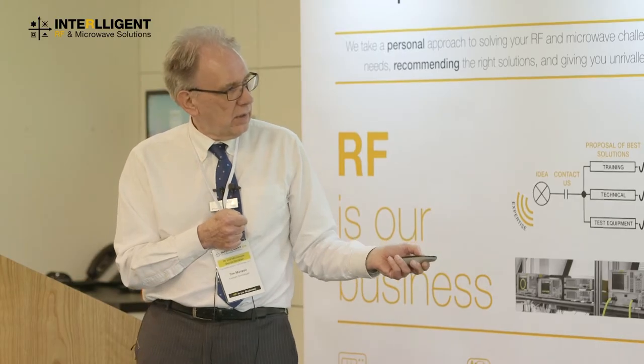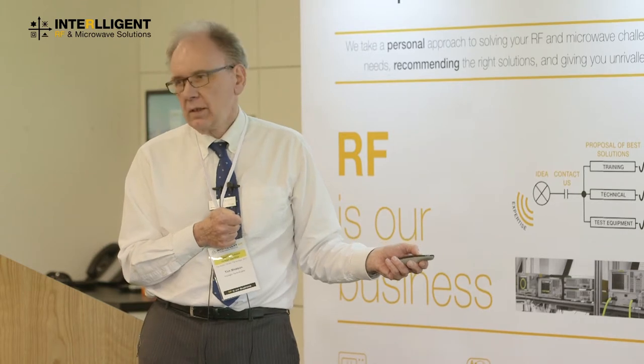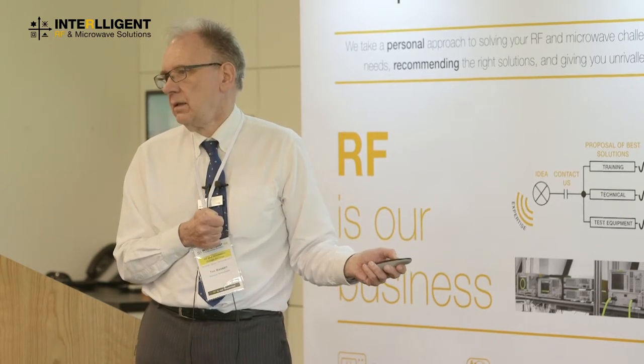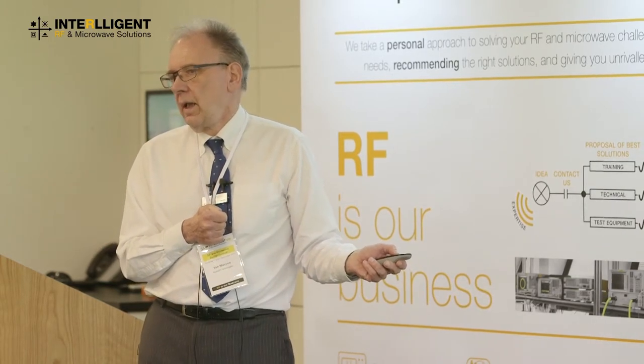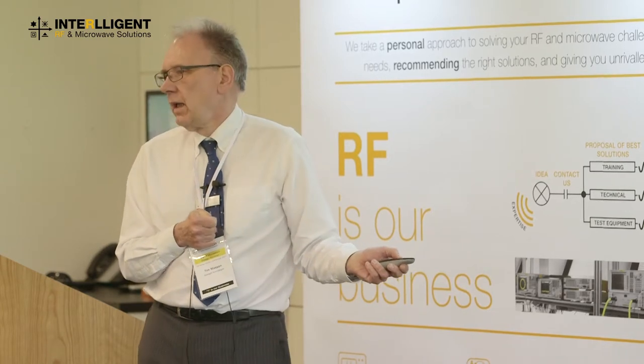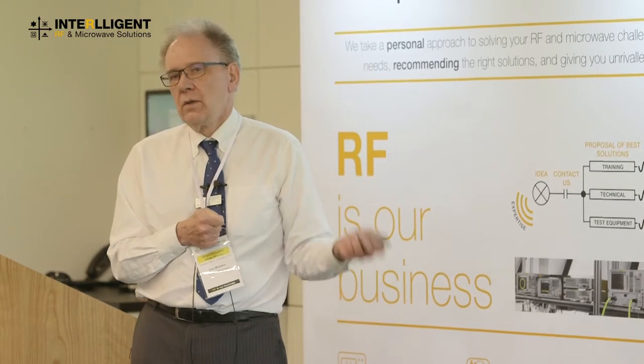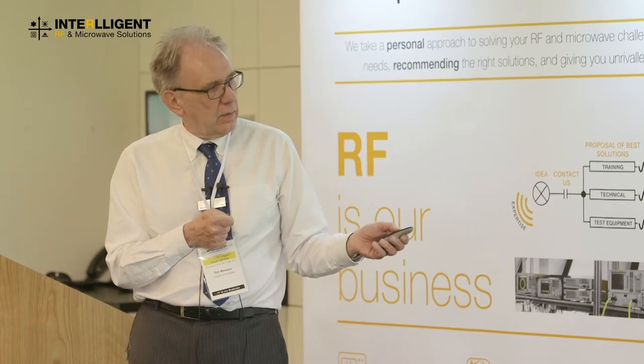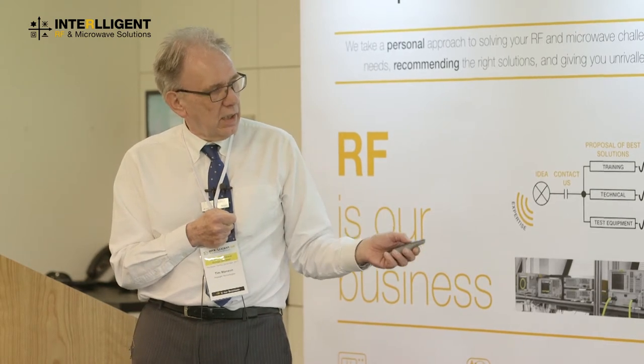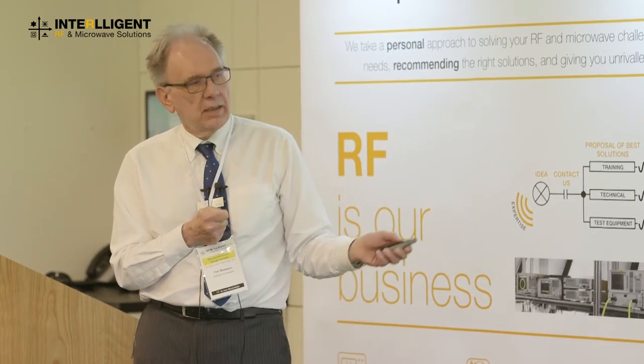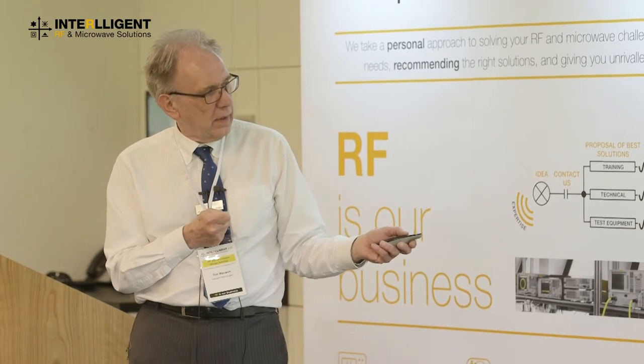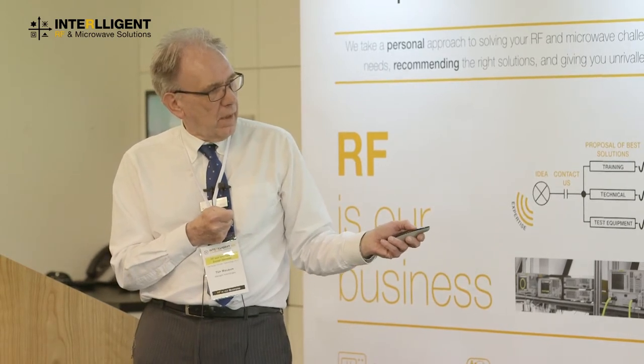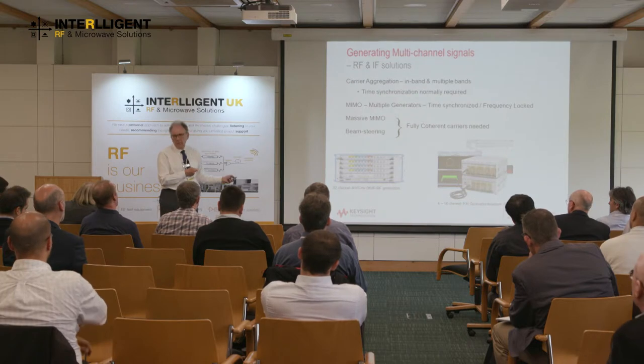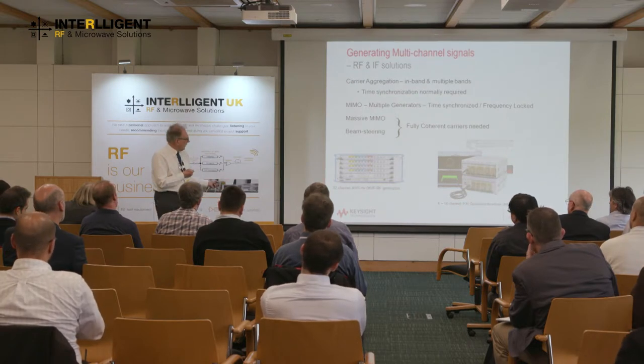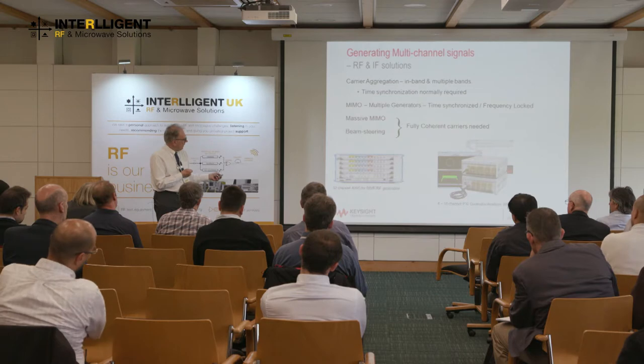With calibration, we can time align signals to about plus or minus a couple of picoseconds, and we can generate those signals at a couple of gigahertz. If you now wanted to up-convert those, they could stay with the same time alignment, or we could calibrate it at whatever frequency you wanted it to be calibrated at, but up-conversion becomes another challenge. So time alignment is really good there.